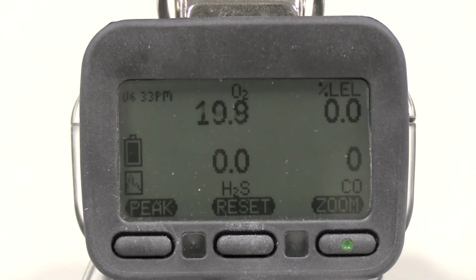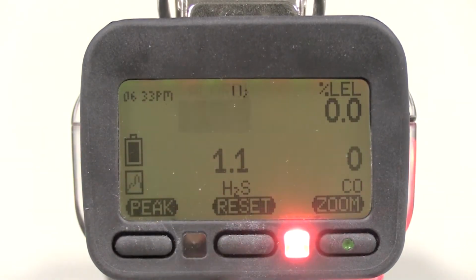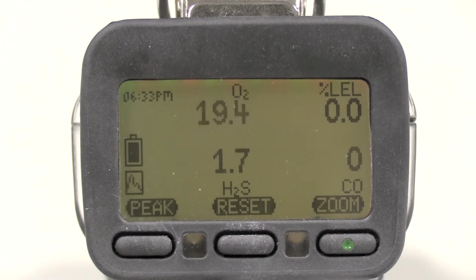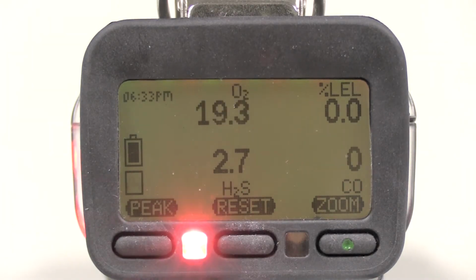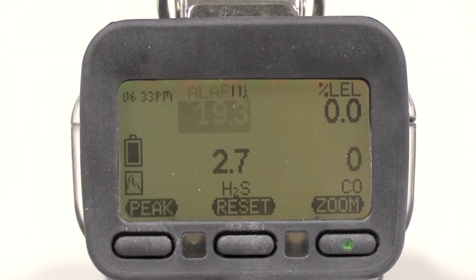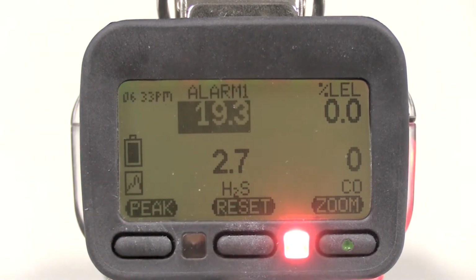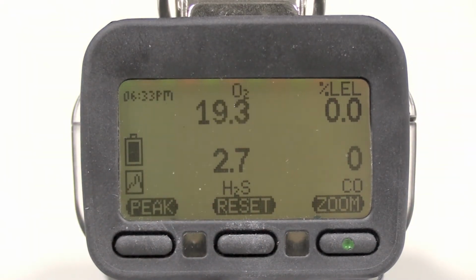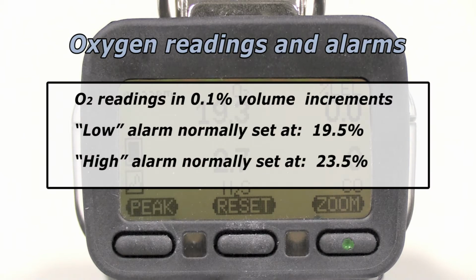Oxygen readings are in percent volume. Readings change in increments of 0.1%. If the concentration drops below 19.5%, the air is oxygen deficient, and the O2 deficiency alarm will be activated. High concentrations of oxygen can also be dangerous due to enrichment. If the oxygen reading reaches 23.5%, the atmosphere is oxygen enriched and the high alarm will be activated.